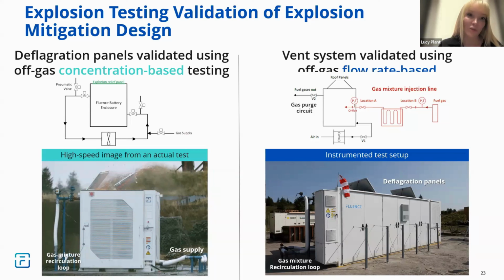We'll also produce CFD models for this, so we know the gases that will come off during one of these events. With that CAD model, we can then model the distribution of those gases. If you have a community living close by, they can understand what's going to come off, what they need to be concerned about, if there's a predominant wind direction, how those gases are going to spread before the true thermal runaway event occurs and those gases are burned up in the process.